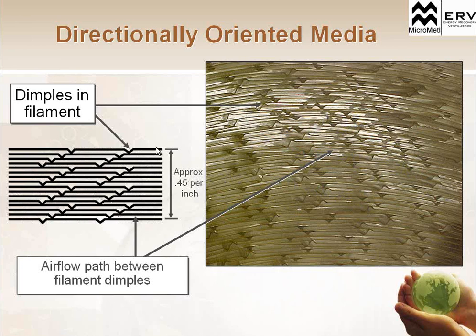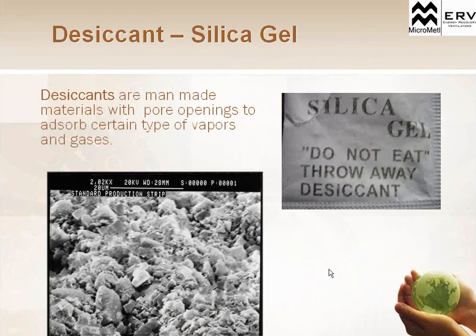You can kind of see very small, thin pieces of plastic packed very tightly together here, about a half inch. And these plastic pieces in these segments of the wheel are lined with a desiccant. The desiccant is actually like a silica gel. If you think of your shoe boxes, or when you buy purses, there's that little packet of silica in the bottom. You know, it says do not eat this packet. What that silica is in there for is to absorb any moisture in that box to prevent your item from getting wet or getting moist.